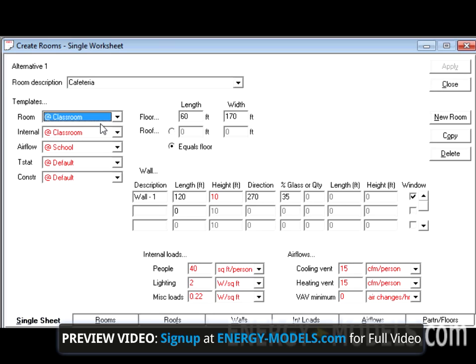Upon selecting the room template, we may enter the room length and width. This determines the room square footage, which determines the building geometry. As we enter data, it becomes evident why Trace cannot display the building, as most data is entered in only two dimensions, and the visual representation requires X, Y, and Z data. In Trace, the floor length and width is only understood by the program as a total square footage. As a result, you can simply enter the room square footage and 1.